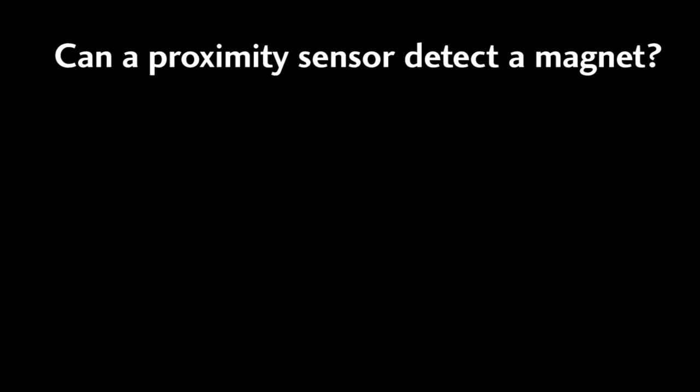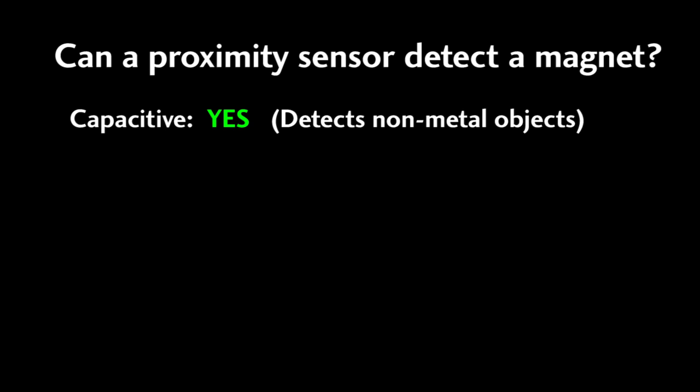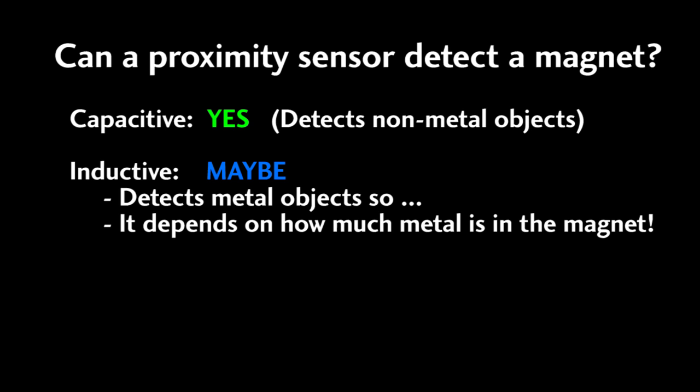Will a magnet trip a proximity sensor? Well, it can. If you have a capacitive sensor, the answer is yes since they detect non-metal objects. If you have an inductive sensor, the answer is it depends on how much metal is in the magnet.